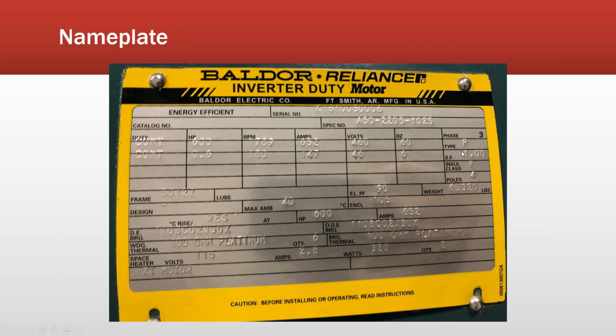Most inverter applications, this is specifically an inverter duty motor, but if you apply a motor on an inverter and it has a 1.15 service factor, based upon design rules, both IEC and NEMA, that becomes 1.0. Okay, and a 1.0 you have to derate as well. All has to do with temperature. Okay, so 5012Z frame. It's a good size machine. It's got some issues. I know that already.